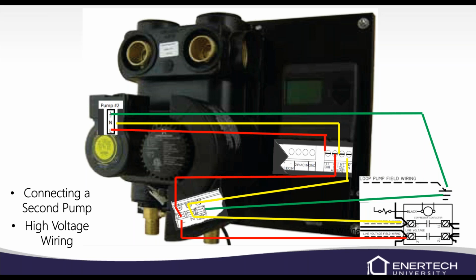So don't just take it from the variable speed pump to the fixed speed pump, or the fixed speed pump will run all the time. Let the controller decide if it needs to run that pump.